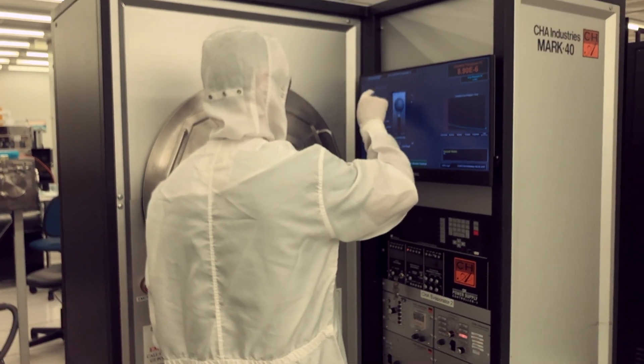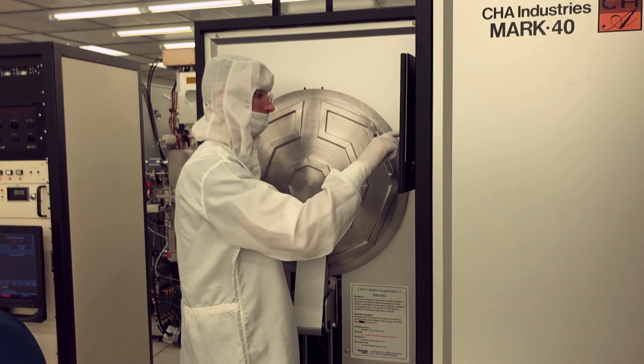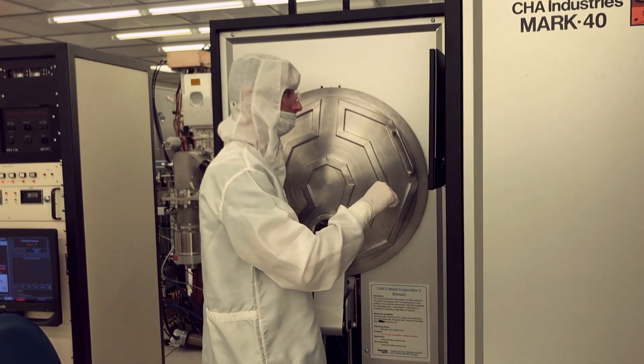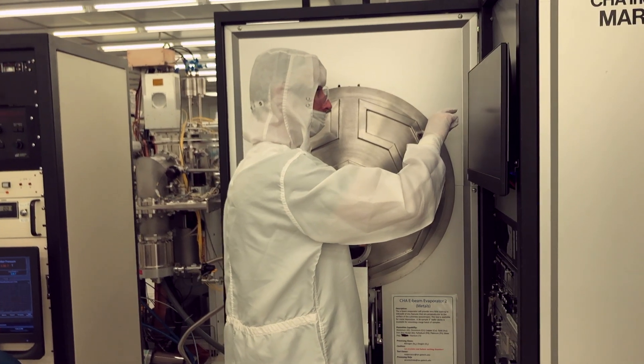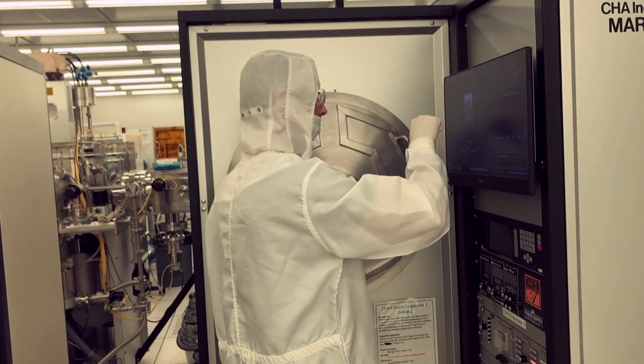Finally, the touchscreen monitor is located above all of the other controls and has various functions. The chamber and cryopump pressure can be viewed at the top right corner of the screen. Venting and pumping down the chamber are controlled on the screen, as well as enabling the process and controlling the shutter.